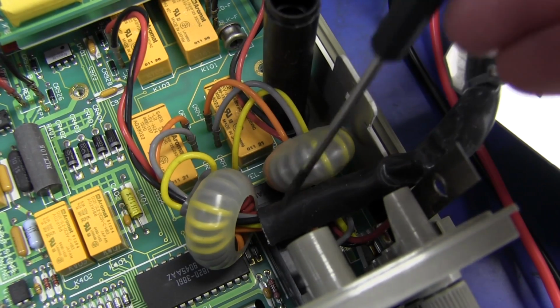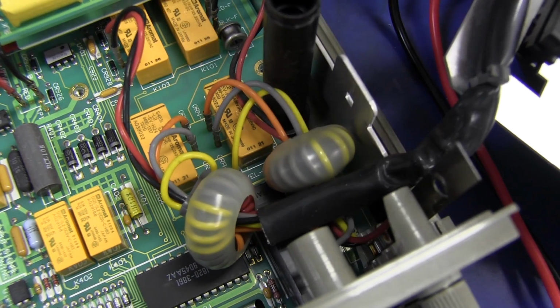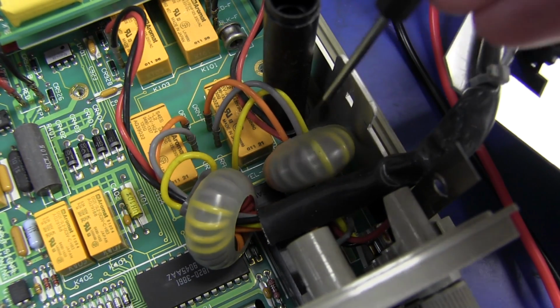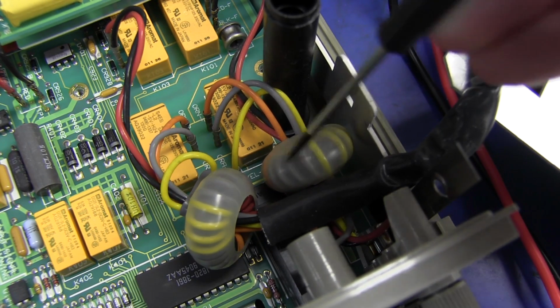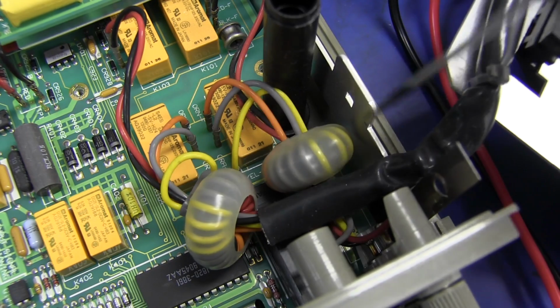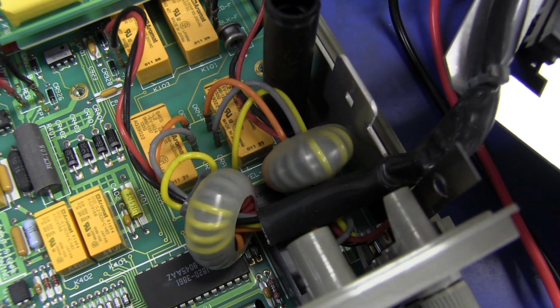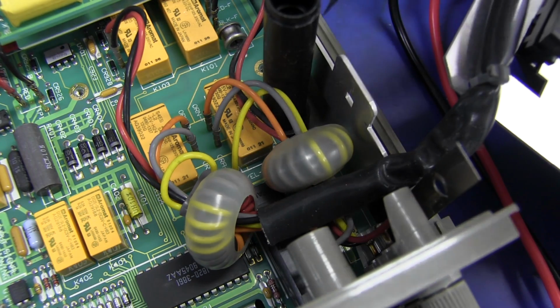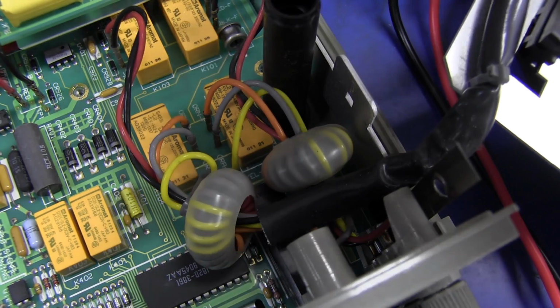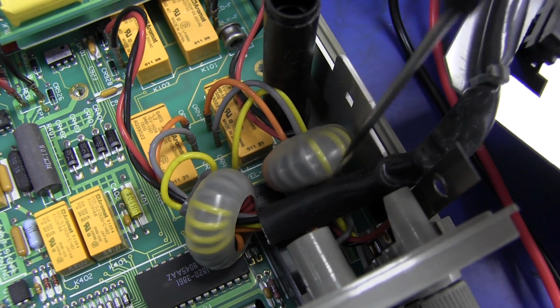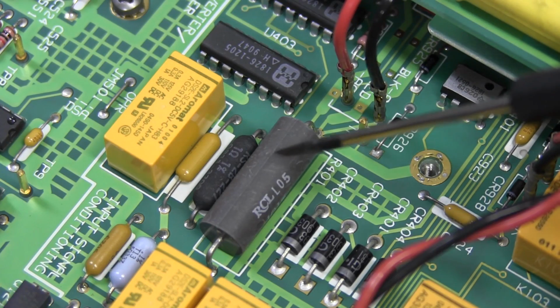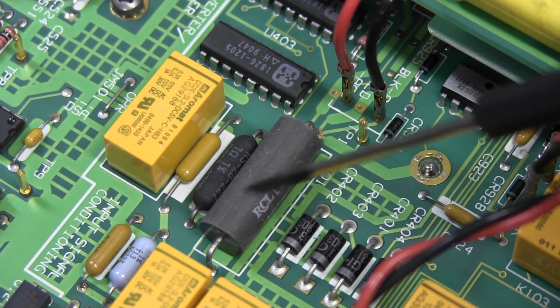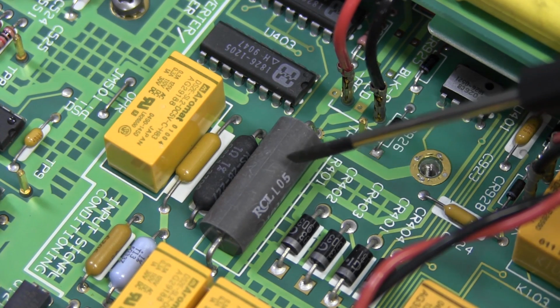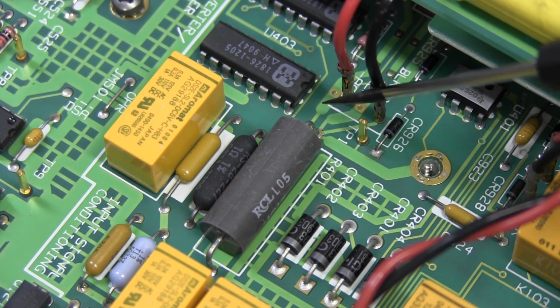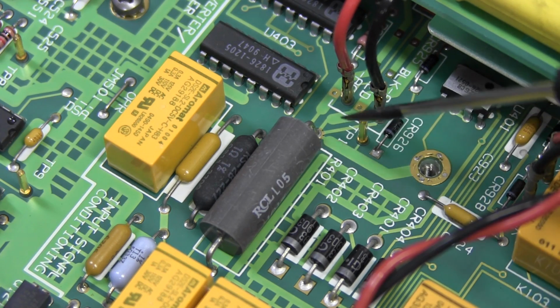And if you have a look at the input terminals down in here, yes, they are just wired directly across like that, but they do go through a toroid filter. They're wrapped around in there, quite nicely heat shrunk down in there, and then they go directly into the relays. But because this thing is all metal, grounded, shielded, stuff like that, you can get away with effectively quite long leads going from the input terminals. And there's a 1.1 ohm high value resistor. That's most likely our input current shunt resistor, and you'll notice all the star grounding branching off from that point. It really is quite nice.